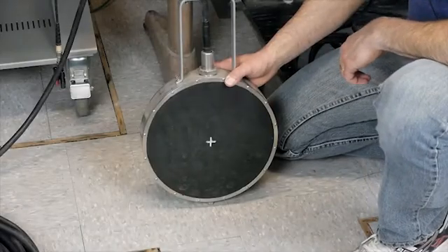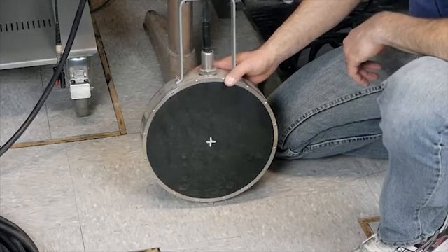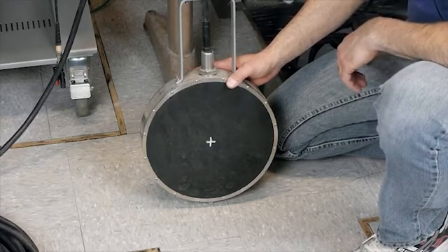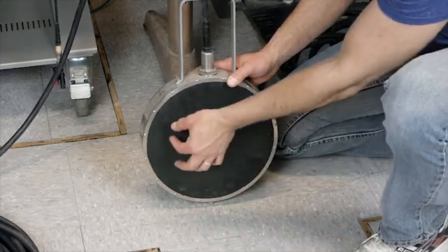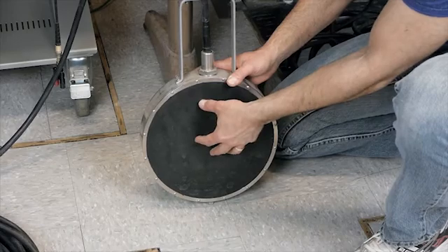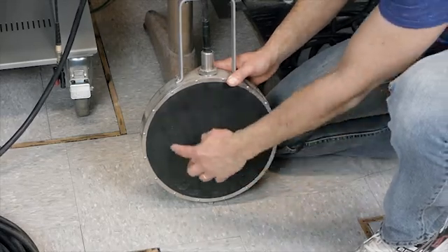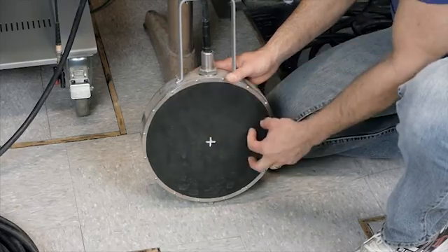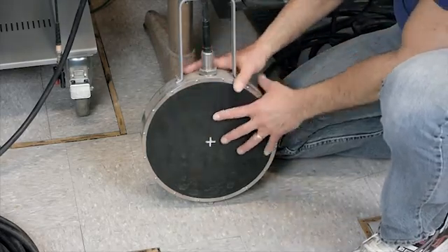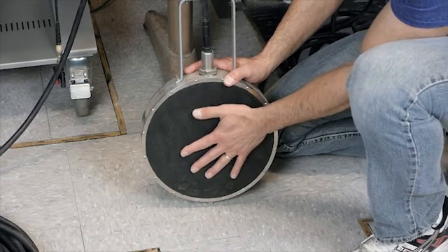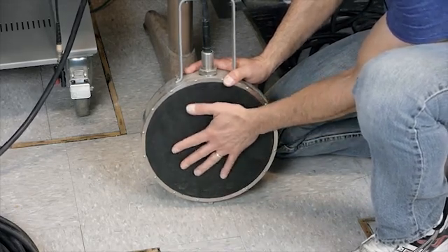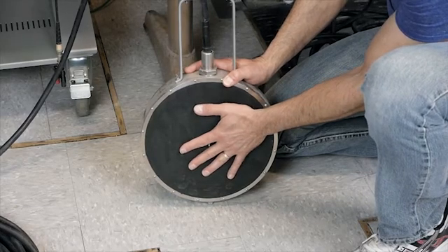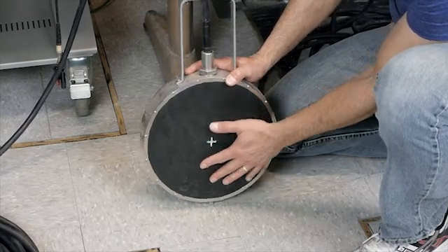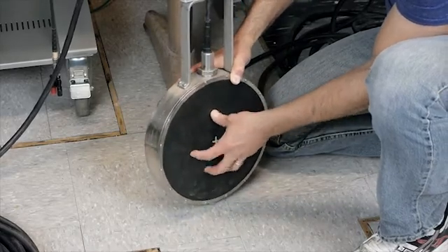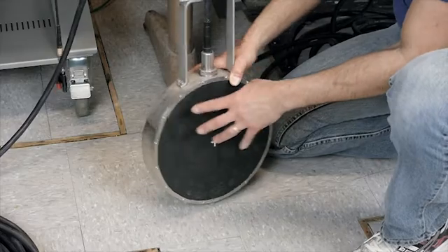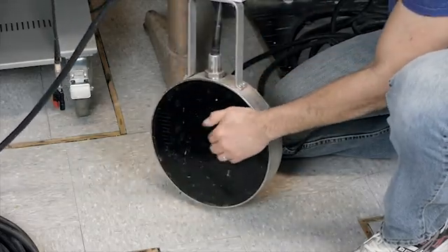The F33 hydrophone is actually a pretty old design. It's made up of a bunch of small piezoelectric blocks that are spread around inside here in an array. And there's actually two arrays. There's a center array and then an outer ring array. The hydrophone is then potted with oil, and then there's a flexible membrane stretched across the surface here. So the oil acts as an impedance match to the water. So what you'll notice is that one side is soft. This is the transmitting side. And then the back side is just a hard urethane.